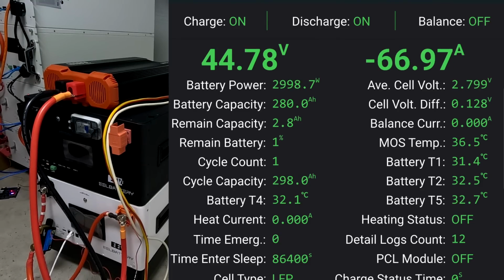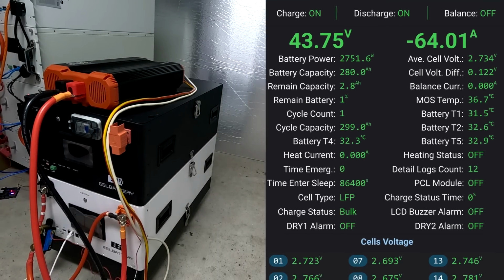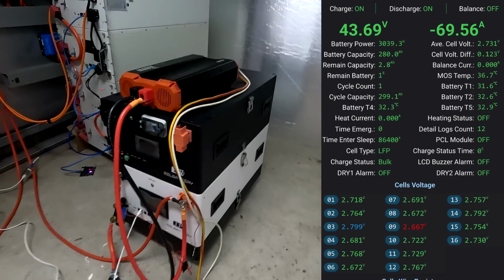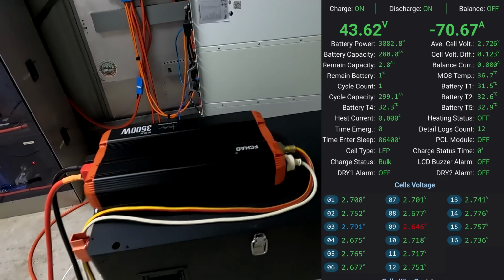Alright, we are not too far away from a shutdown, and then the BMS will disconnect both inverters at the same time. Okay, 43 volts, I can hear the inverter running hard now. The fans are slowing down.